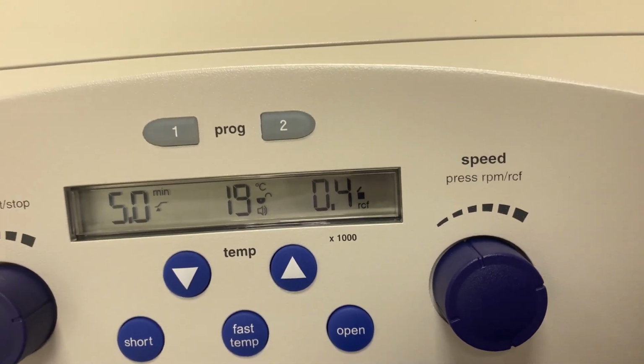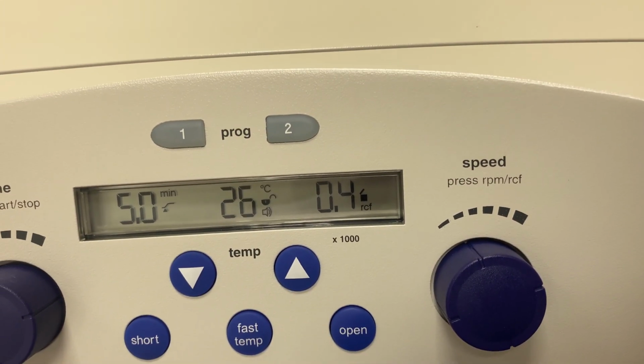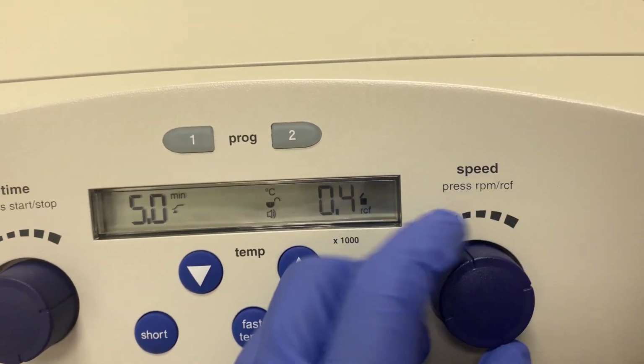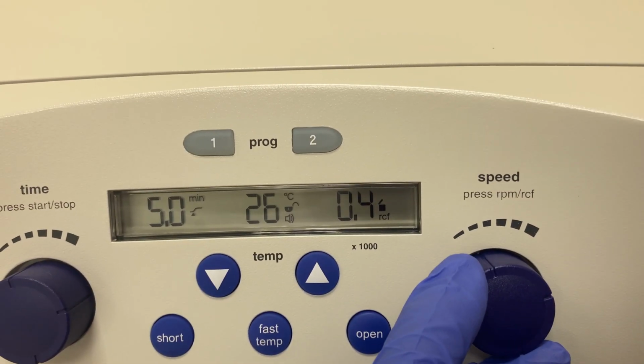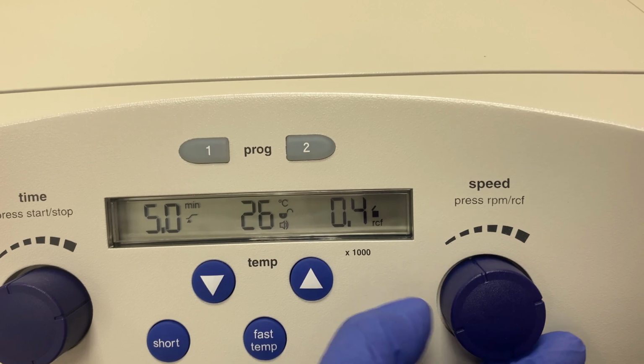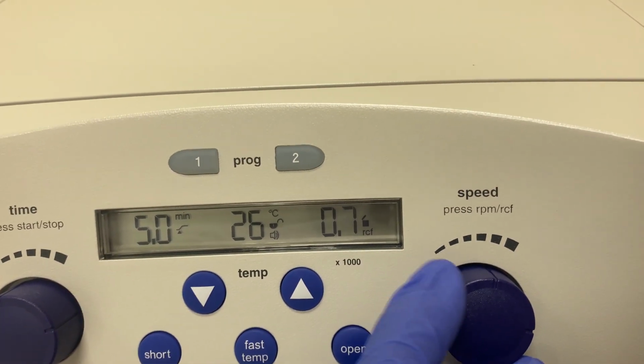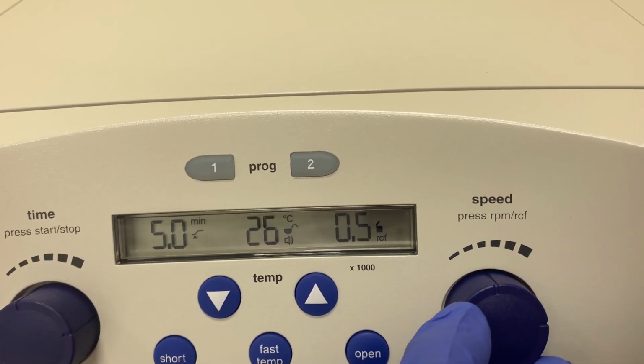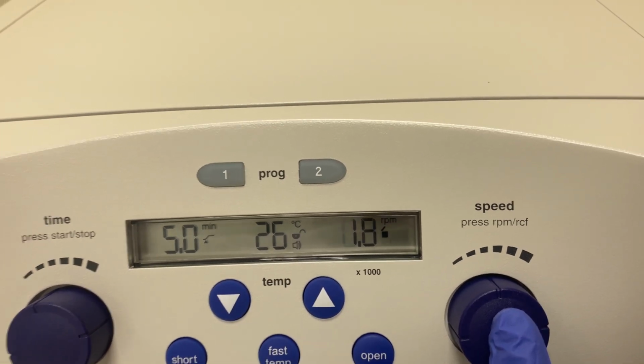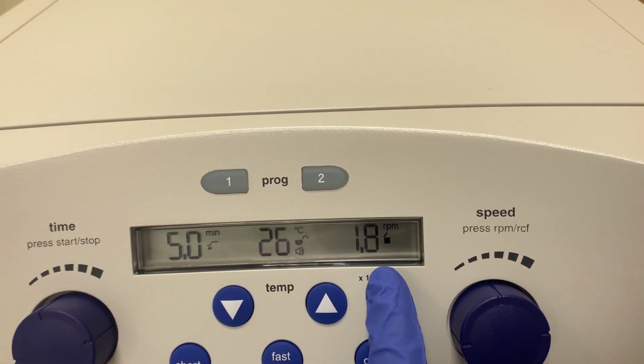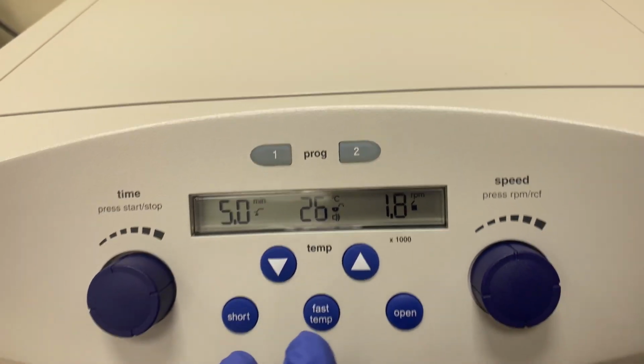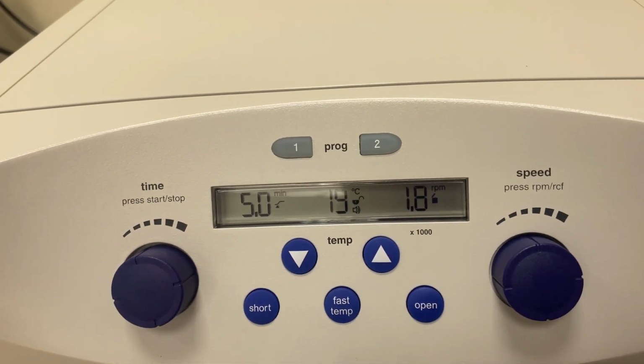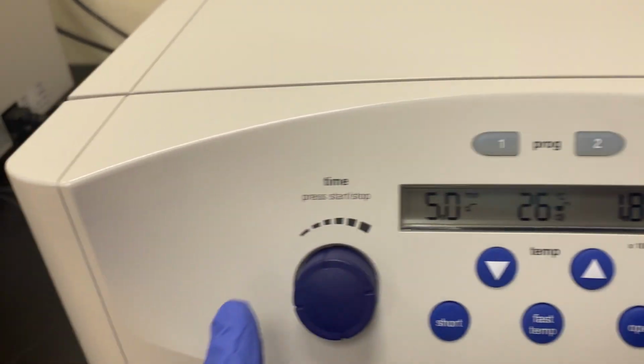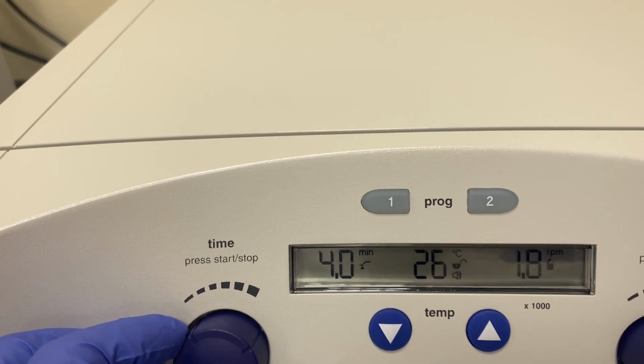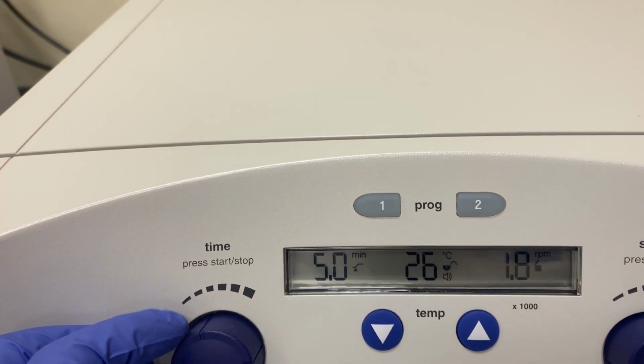If you want to spin at, let's say, 500 G, you rotate clockwise to increase and counterclockwise to decrease. 500 G equals 1800 RPM. Every machine will have a different conversion, and you can also change the length of the spin.